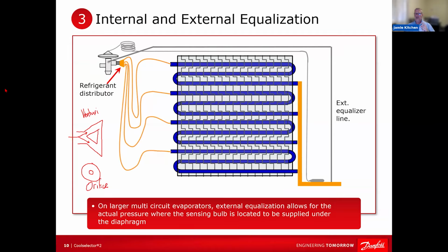So the rule is you can use an external equalized TXV even if you don't need it, but you can never use an internal equalized one if you need an external equalized one. In other words, if you have a distributor, you need an external equalized one. And remember, even if you don't need that external equalization connection, you still need to connect it to the evaporator. Don't plug it off, otherwise it'll never open. Okay, so make sure you do.